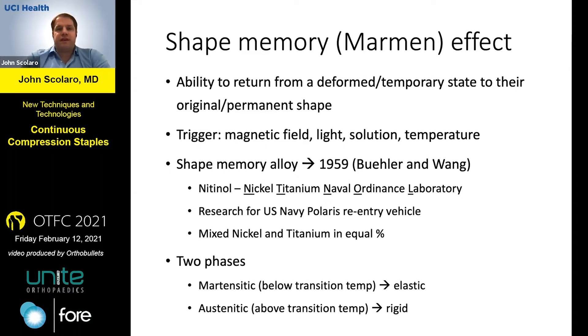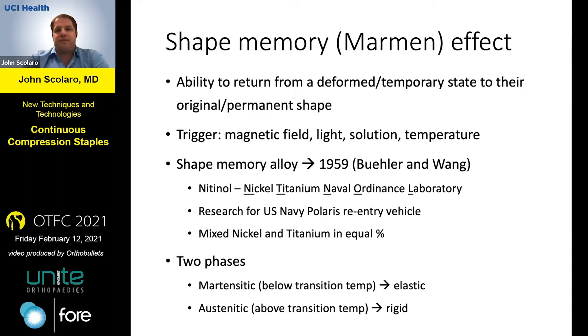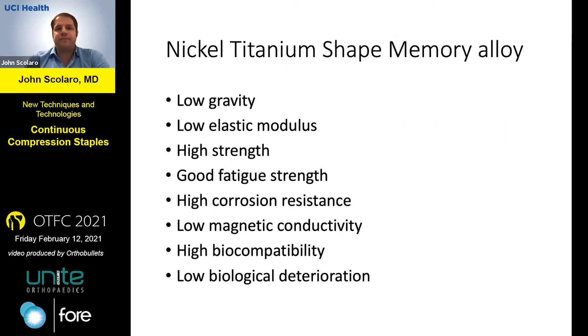There are two phases if you get into the nitty-gritty of this technology: the martensitic and the austenitic. These terms describe the alloy below the transition temperature — where the metal is very elastic — and then above the transition temperature, where it becomes much more rigid. This is what gives these compression staples significant rigidity after they've been placed into the human body.